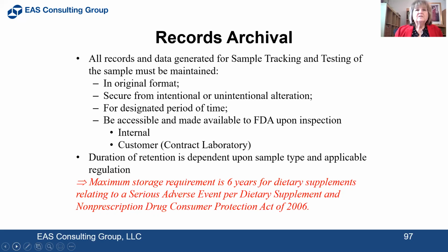It must be accessible and made available to the FDA upon inspection, whether it's internal or a customer for a contract laboratory. The duration of retention is dependent upon the sample type and applicable regulation. So the maximum storage requirement is 6 years for dietary supplements. That's only when it relates to a serious adverse event per the Dietary Supplement and Non-Prescription Drug Consumer Protection Act of 2006.